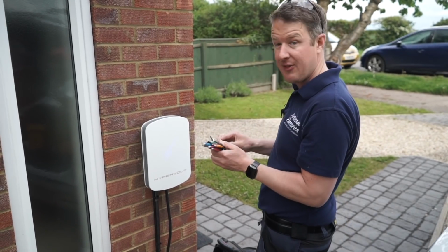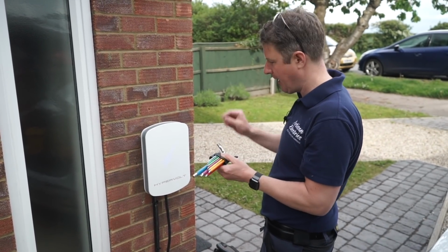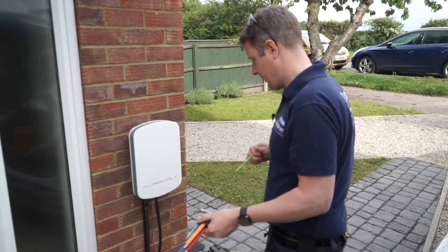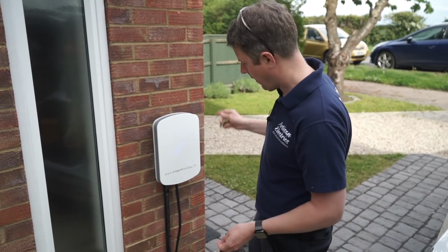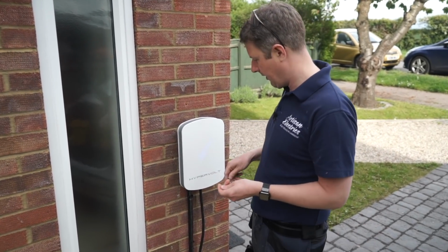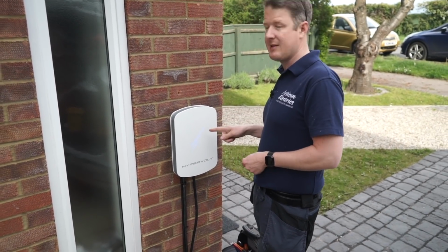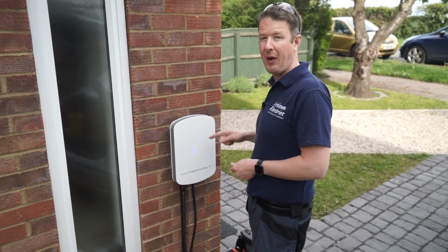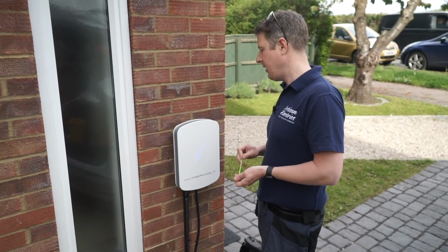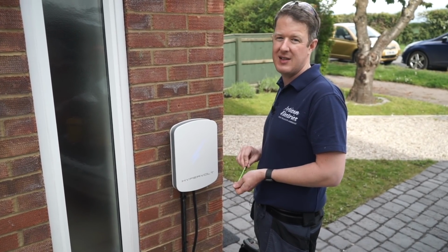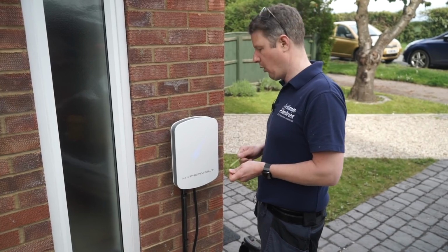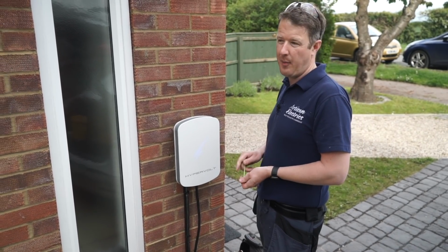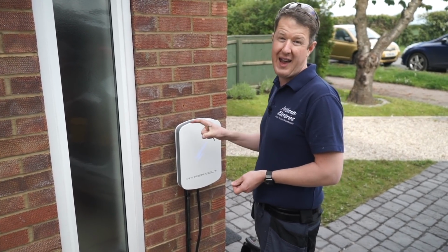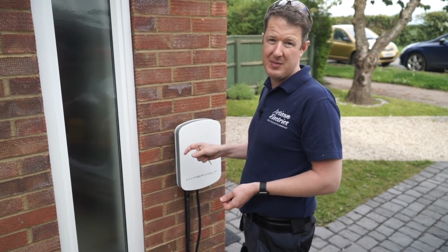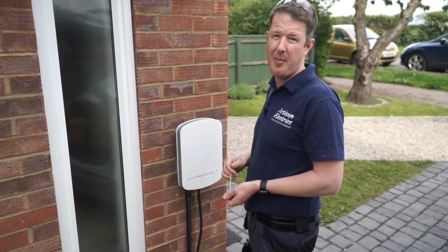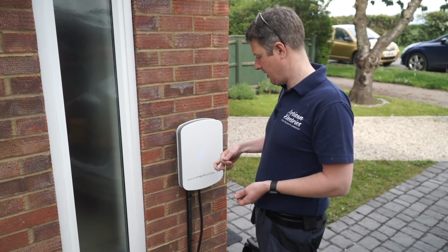In terms of safety features, this has pen fault detection built in, which means you don't need an earth rod. You can install it directly off a circuit, but it will need a type A RCD to protect it. It's got built-in 6 milliamp DC protection, so you don't need an expensive type B RCD, but you do need a type A RCD. Normally the regs recommend a double pole, so you'll probably need a separate enclosure with a type A RCBO or a 32 amp MCB, and then out of that into a type A RCD just to protect the charge point.